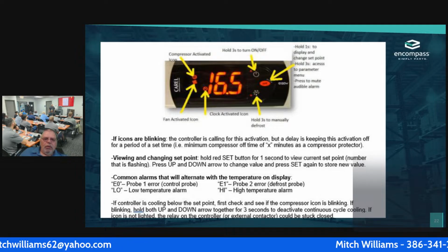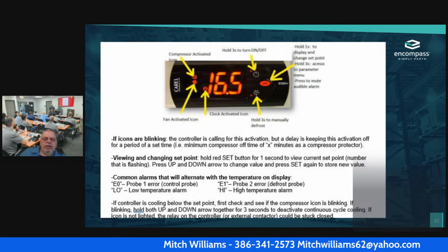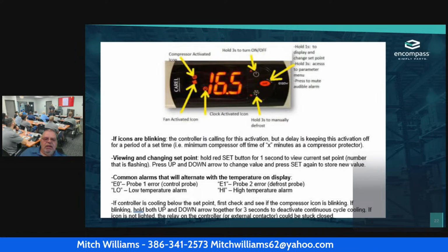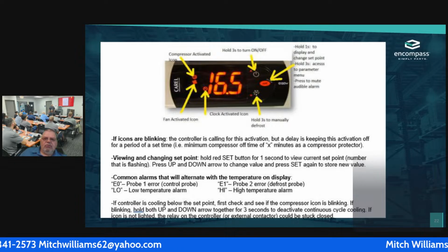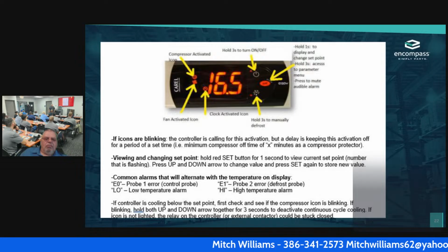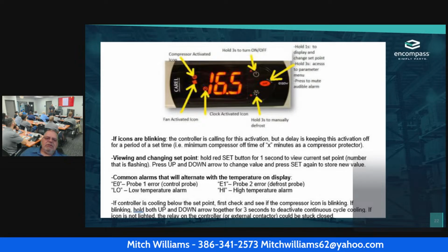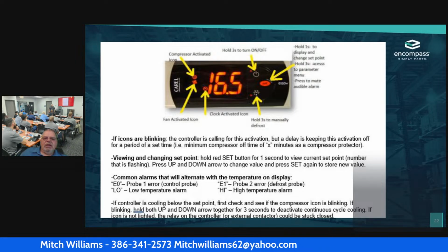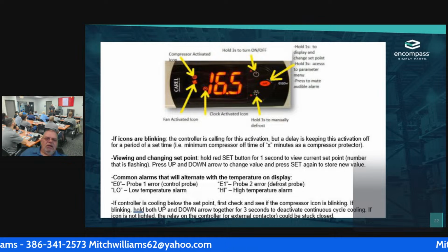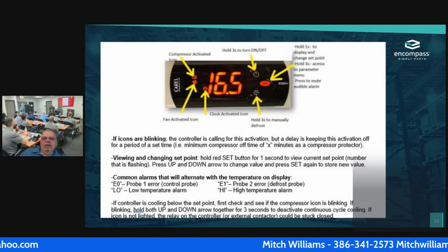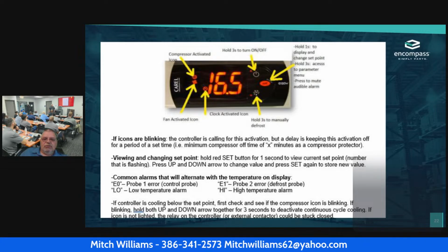Okay. Common alarms will alternate with the temperature on the display. If I get an E0, it's got a probe error. Okay, that's my control probe. So I'm going to have to go and check my control probe. The first thing that I'm going to check is to see if it's unplugged. The next thing I can do is a continuity check and see if that probe is any good. If the probe comes back at infinite, I know that I have an issue.